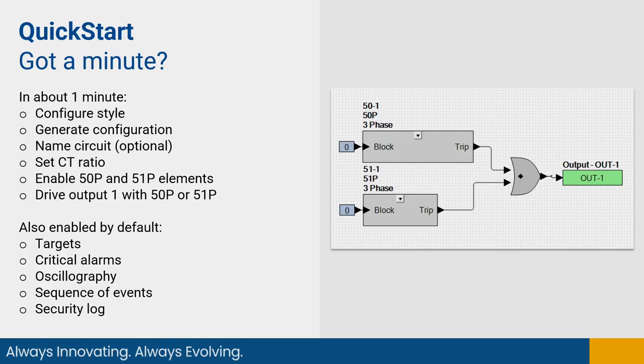The next step for this typical overcurrent application, you would create a 50 and a 51 element, the instantaneous and time overcurrent elements, and then complete the settings for these 2 elements. This would automatically create targets, oscillography via fault records, sequence of events, and a security log.